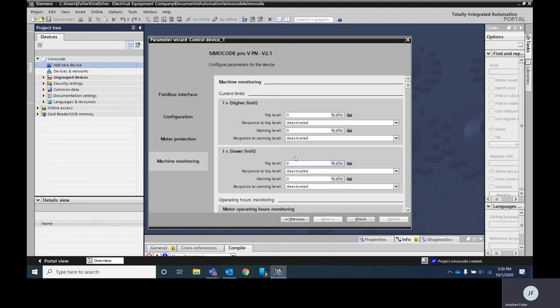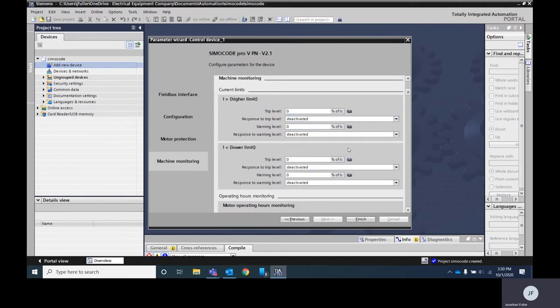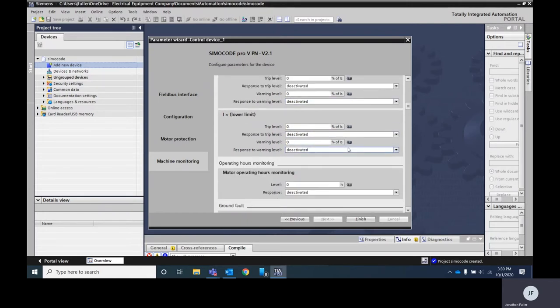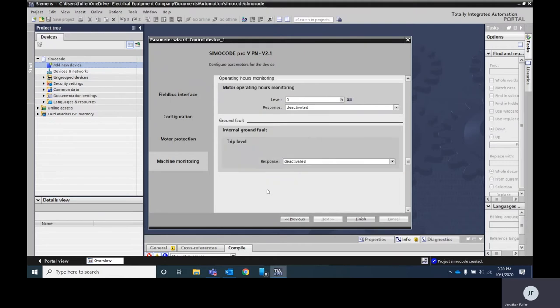This screen is for your machine monitoring. Again you're going to be entering in some different information as far as current for your limits. You can set warning or alarm if you've entered a certain amount of hours on your motor. You can do ground fault with this unit. Once you've got those settings done you go ahead and hit finish.